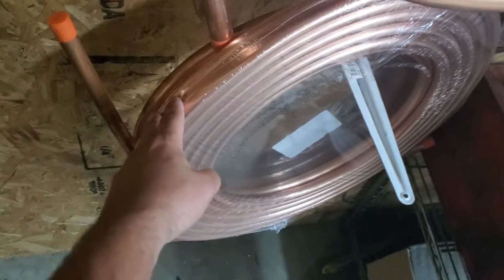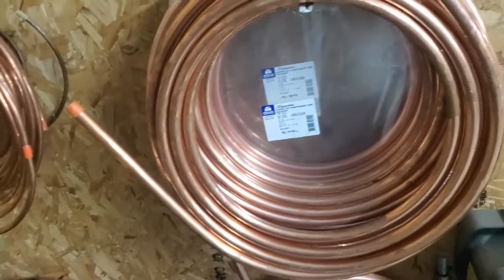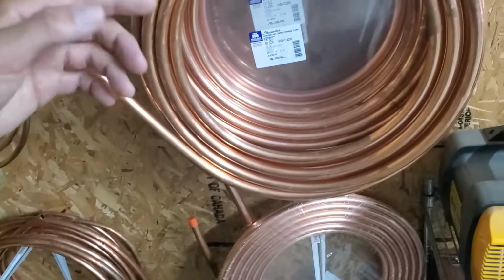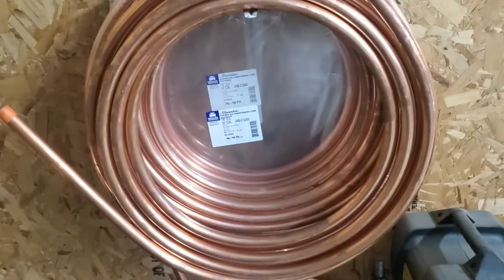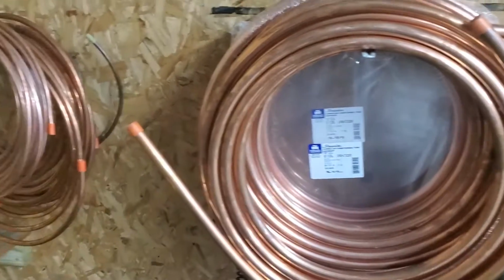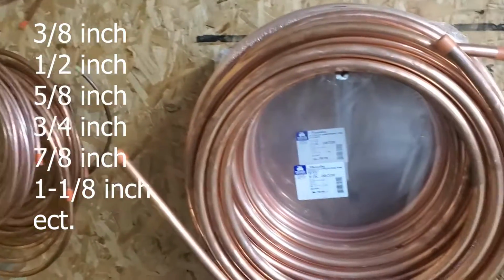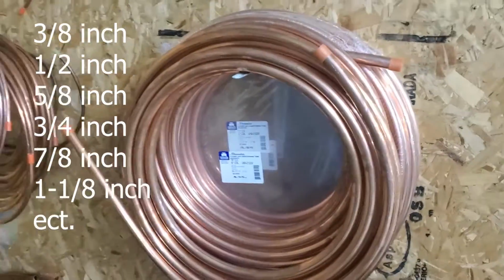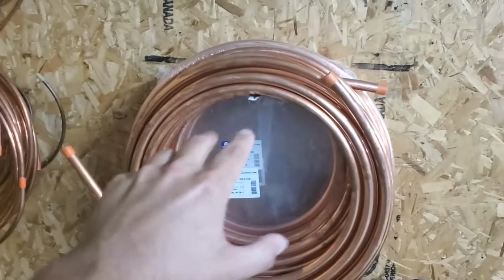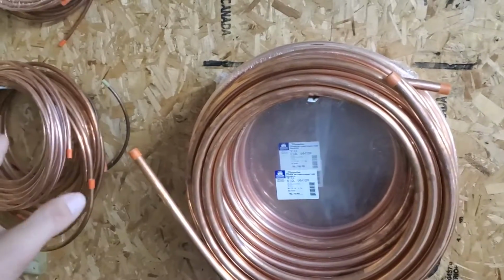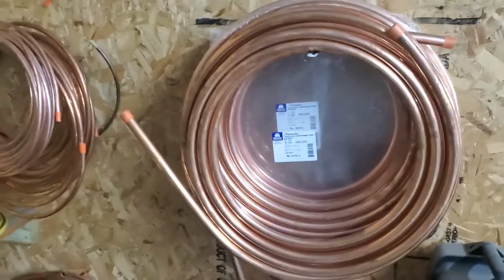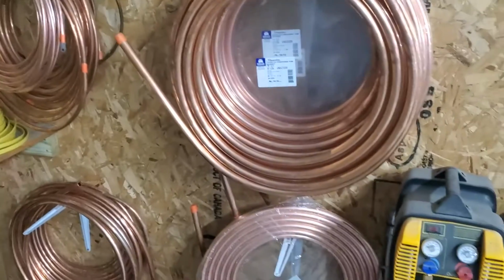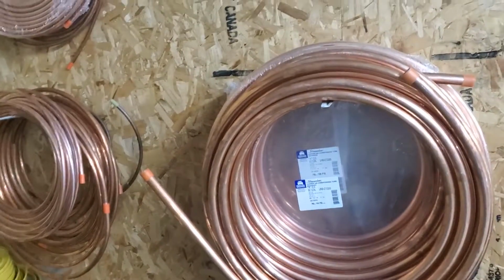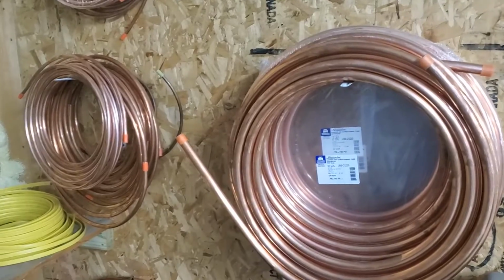This right here is 3/4. So you've got 3/8, 1/2 inch, 3/4, and 7/8. And you need to know your copper sizes. All equipment has an outlet on the condenser, and it has to match the copper size that's required for it. Otherwise, your capacity will change. Your velocity will change. You will not be able to adequately pump the refrigerant through the system. So definitely know your different copper sizes, guys.